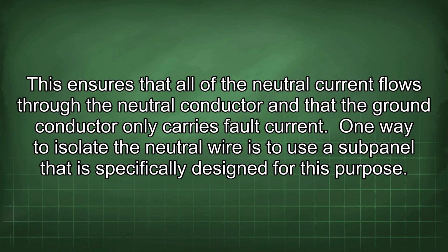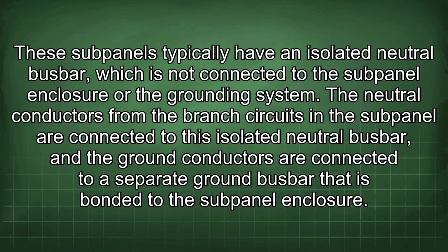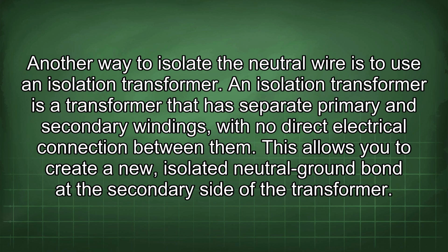This ensures that all of the neutral current flows through the neutral conductor and that the ground conductor only carries fault current. One way to isolate the neutral wire is to use a subpanel that is specifically designed for this purpose. These subpanels typically have an isolated neutral busbar, which is not connected to the subpanel enclosure or the grounding system. The neutral conductors from the branch circuits in the subpanel are connected to this isolated neutral busbar, and the ground conductors are connected to a separate ground busbar that is bonded to the subpanel enclosure. Another way to isolate the neutral wire is to use an isolation transformer. An isolation transformer is a transformer that has separate primary and secondary windings with no direct electrical connection between them.